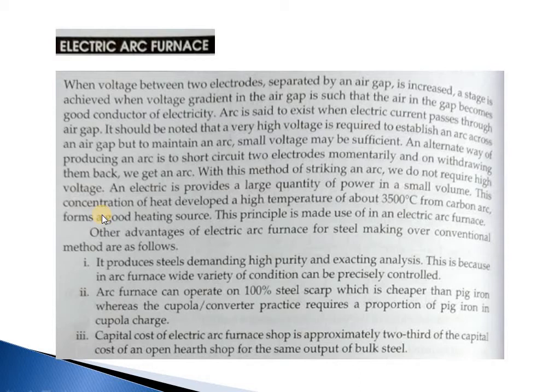It should be noted that very high voltage is required to establish an arc across an air gap, but to maintain an arc, a small voltage may be sufficient. An alternate way of producing an arc is to short-circuit two electrodes momentarily and on separating them back we get an arc. With this method of striking an arc, we do not require high voltage. An arc provides a large quantity of power in a small volume; this concentration of heat develops a high temperature of 3500 degrees centigrade. So carbon arc forms a good heat source.